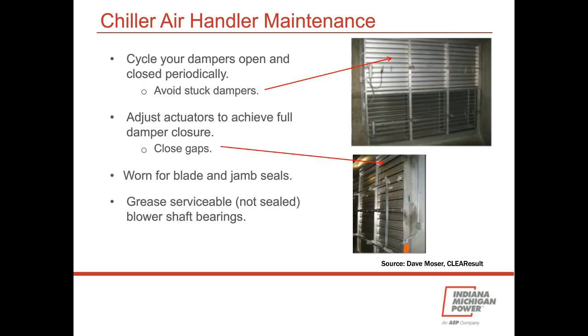All right, air handlers. Outside air dampers, well, they're moving parts, they're outdoors in the weather. They can seize in place due to entering debris or humid conditions, and the linkages can fail. So you really want to cycle your dampers open and close periodically and verify that they operate as intended.